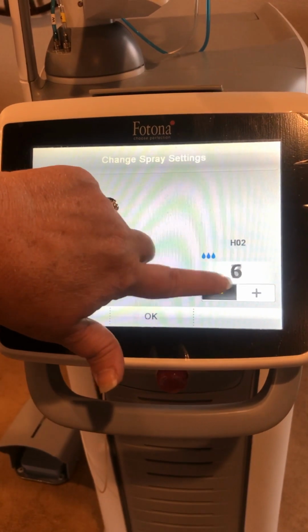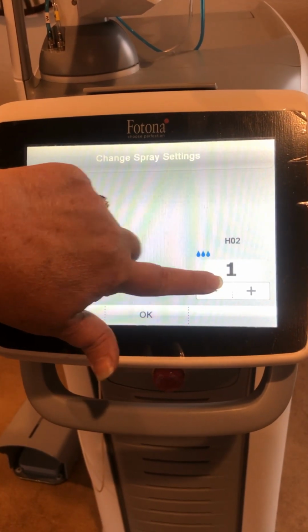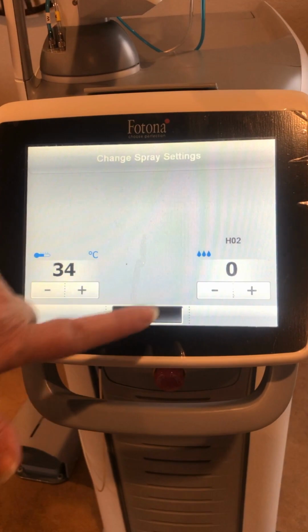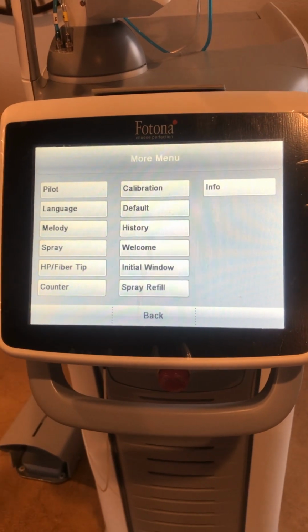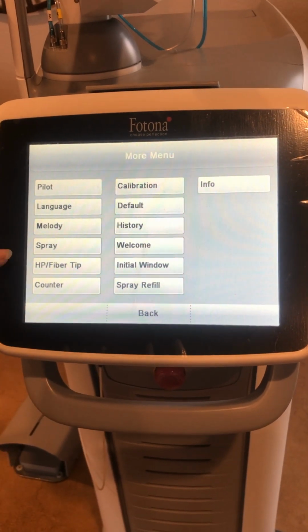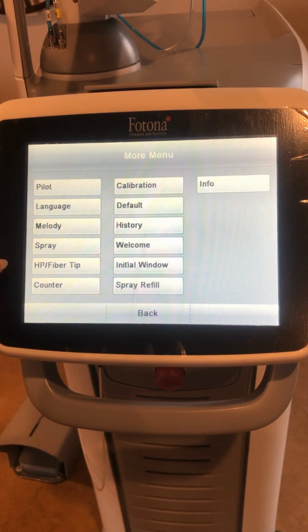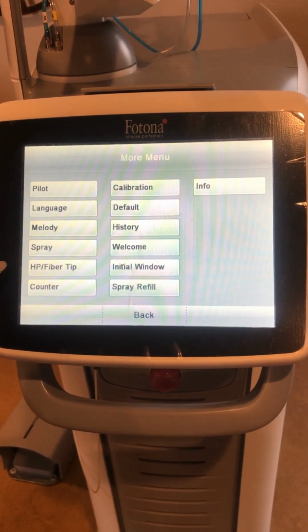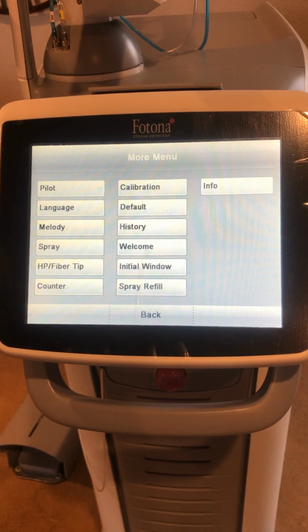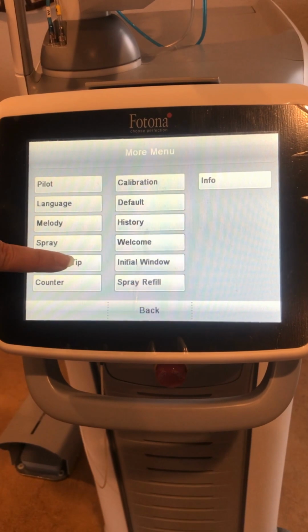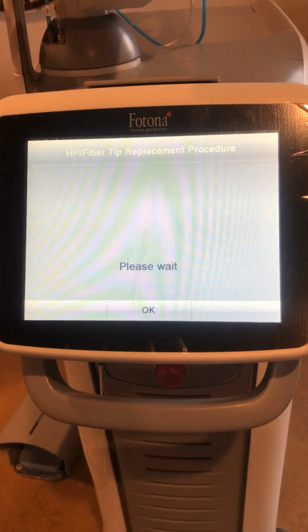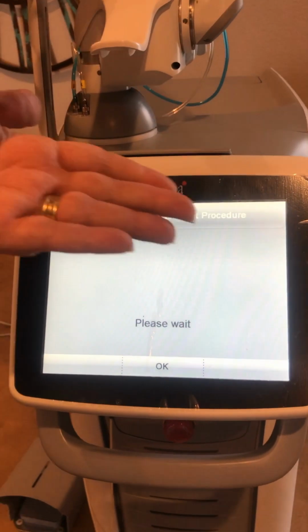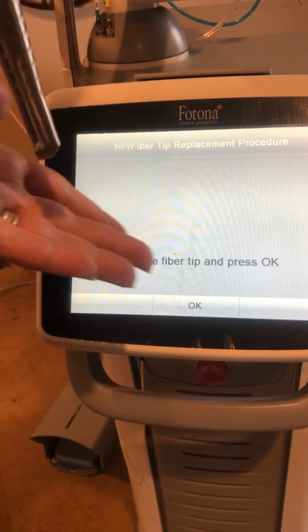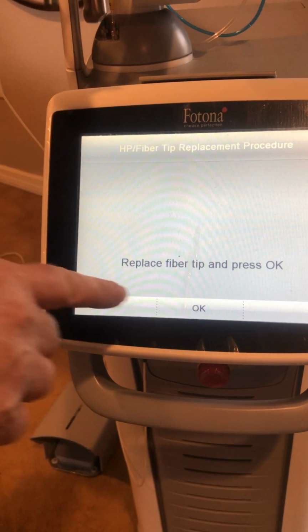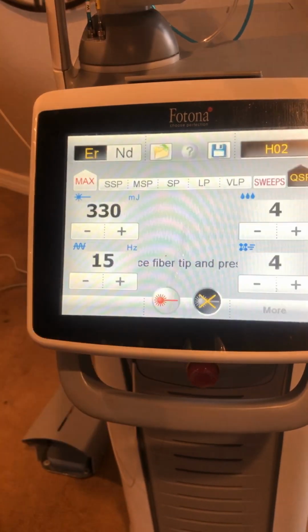Generally, you want to set this at 0 and let it be, so that the settings you do on the screen are set from a baseline of nothing. HP fiber tip is the button you hit when you need to change handpieces, and it forces air. So I'm going to hit this button, and now it's putting air out of the handpiece the whole time while I'm changing the handpiece. And then when I'm completely done changing the handpieces, I'm going to hit OK, and it's back done.